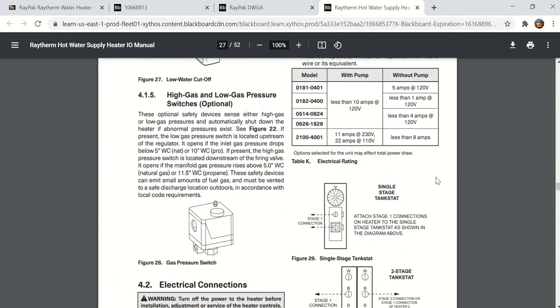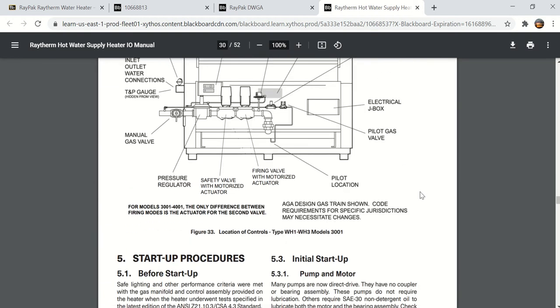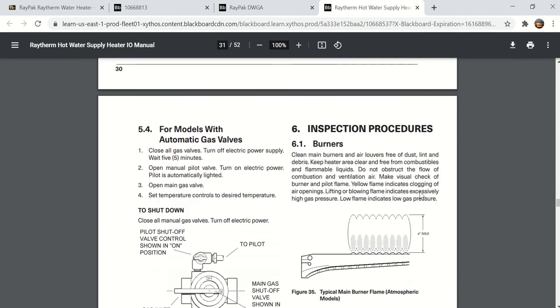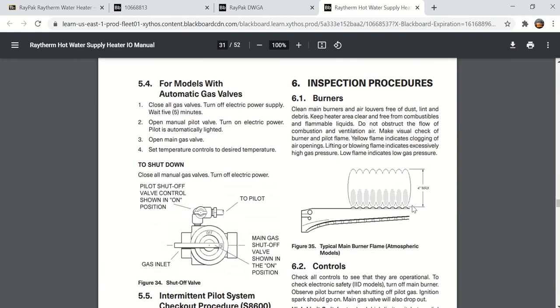The next thing I want to go down to is page 31 here. I'll talk about this because on this particular burner, it's called an atmospheric burner. You see right here where it says figure 35, typical main burner flame for an atmospheric model. So that means that this type of boiler does not have a blower. It doesn't force air into the combustion chamber. It doesn't have an induced draft motor. It was considered atmospheric pressure.